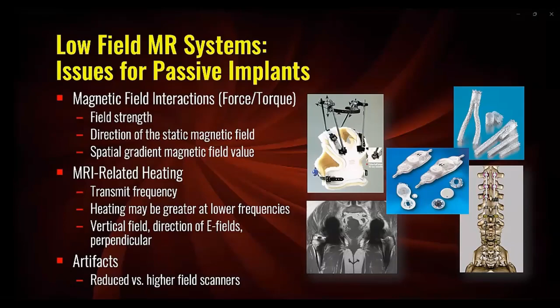With respect to MRI-related heating, the transmit RF frequency impacts the amount of heating that occurs for a given implant, which is predominantly dependent on the implant's length. Notably, heating has been reported to be greater at a lower frequency than at a higher frequency, depending on the length of certain implants. For vertical field scanners, further consideration should be given to the direction of the E fields, which is perpendicular. Importantly, peer-reviewed publications have reported that perpendicularly oriented E fields associated with vertical field MR systems operating at 1.2 Tesla and 49.5 megahertz result in less heating for certain passive implants as well as for active implants. The last remaining issue to be aware of for implants is that artifacts are inherently lower on scanners operating at field strengths lower than 1.5 Tesla.